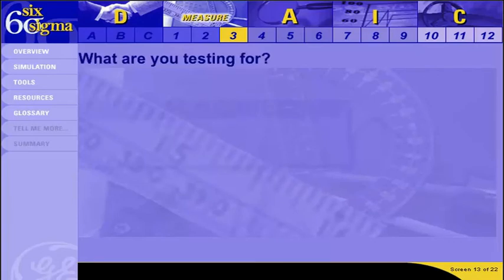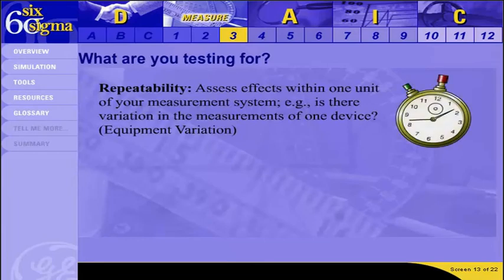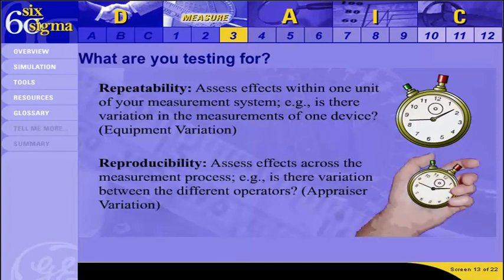Before discussing the tests themselves, we need to answer: what are we testing for? In two words: repeatability and reproducibility. Repeatability means looking at variation within one component of the process — also known as equipment variation — asking whether one operator measuring the same items several times with the same instrument produces the same measurements. Reproducibility means testing variation across the process — also known as appraiser variation — asking whether different operators measuring the same items get the same results. A good memory aid: there is an E in repeatability for equipment, and an O in reproducibility for operator.